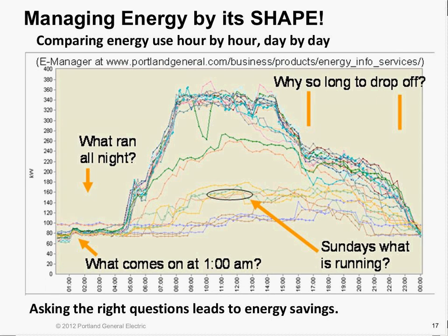What's coming in the future, and the future is now with Portland General Electric, is that we have digital meters on all the homes and offices throughout our service territory that can give you hourly information. So I asked one of my experts in monitoring load software to give me a picture. This is a school. It is 30 days' worth of metering information, and you've got a 24-hour clock at the bottom. So you go from midnight to midnight with noon in the middle. Sure enough, that makes perfect sense: at about 8 o'clock, everybody's at school, and you're at your peak loads.